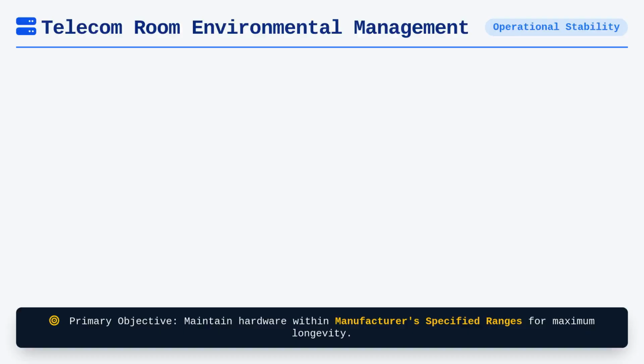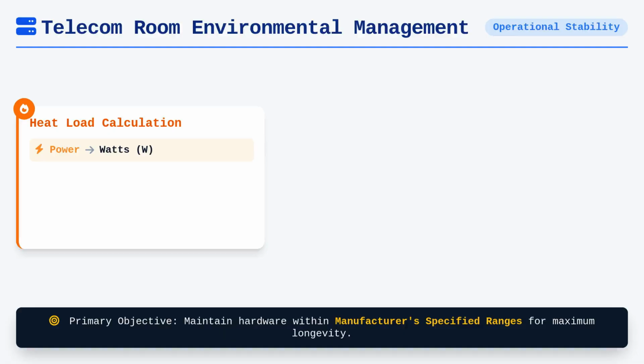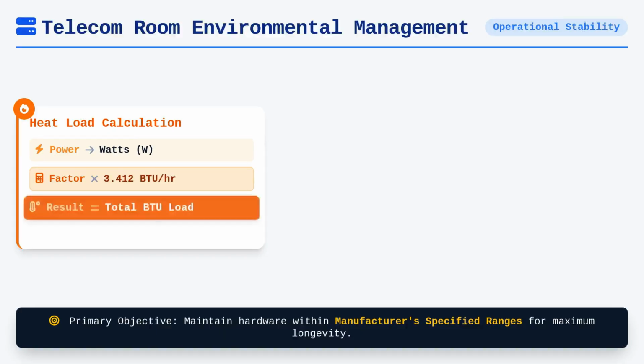The primary objective of environmental management within a telecommunications room is to ensure that active hardware operates within the manufacturer's specified temperature and humidity ranges. We start by calculating the heat load, which is fundamentally derived from the power consumption of the equipment installed in the racks and cabinets. Since every watt of electrical power consumed by a server or switch eventually dissipates as heat, we use the conversion factor of 3.412 British thermal units per hour for every watt of power. If you have a total load of 2,000 watts, you are generating approximately 6,824 BTUs per hour, and your HVAC system must be sized to remove this specific sensible heat load.